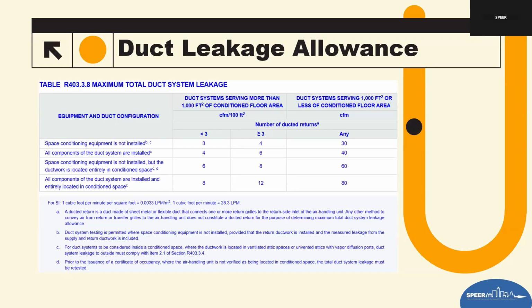And this table rewards tighter duct systems and better duct designs. The more compact systems and fewer ducted returns you have, the easier it is to meet these allowances. Large sprawling systems with multiple returns have higher margins of error and can have a little bit more leakage inside those with more returns.